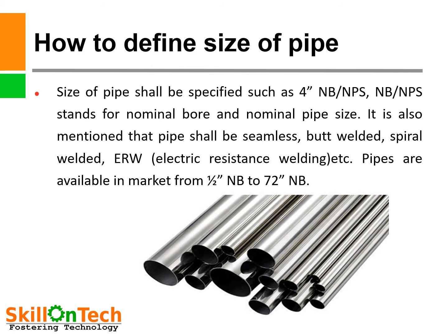How to define size of pipe? Size of pipe shall be specified such as 4 inch NB-NPS. NB-NPS stands for nominal bore and nominal pipe size. It is also important to mention the manufacturing method — whether the pipe shall be seamless or welded, spiral welded, ERW (electrical resistance welding), etc. Pipes are available in the market from 1/2 inch NB to 72 inch NB, so we must specify the correct specification of pipe.